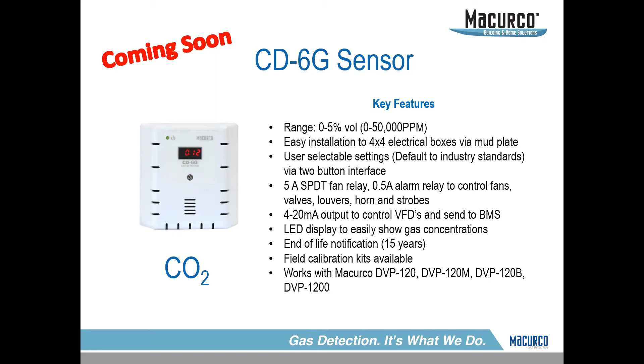Moving into the control panel. A lot of contractors installing these types of systems see a lot of standalone detectors. If they use more than 3 detectors of the same type, so you have 3 CO detectors in one area, we typically will start to recommend using a control panel of ours. The DVP stands for Detection and Ventilation Panel. You can use it in many different ways, but there are 3 dry contact relays on the bottom of this. So we see a lot of these panels being sent to the fire panel with a single location of what's going on in the detector world.